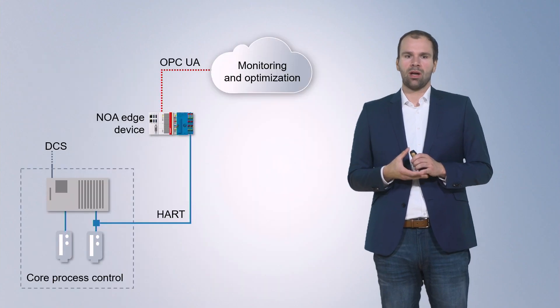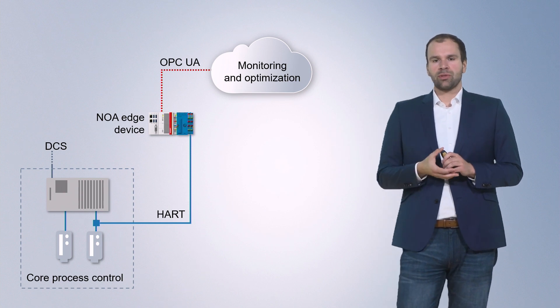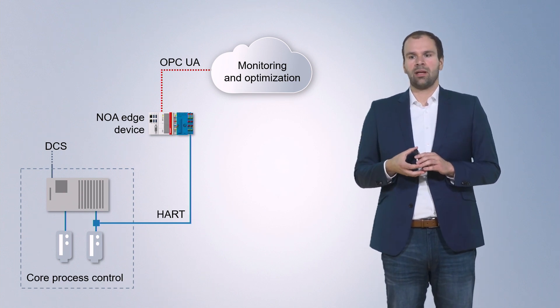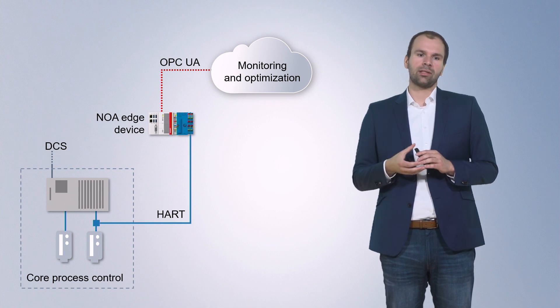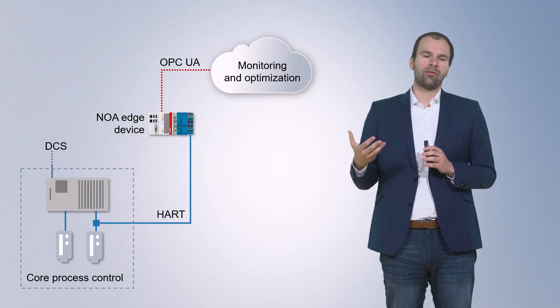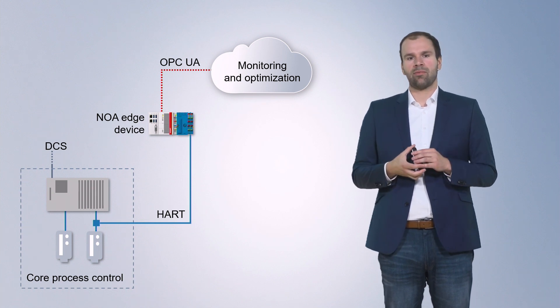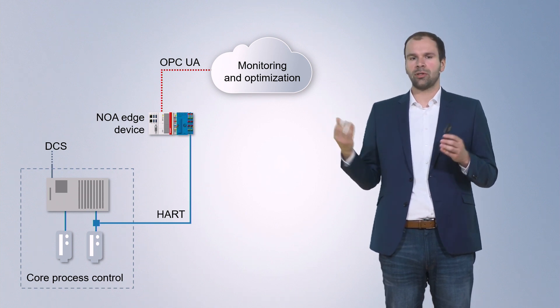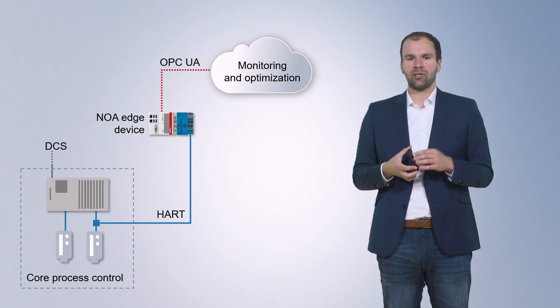This data is then converted inside the edge device, and provided through a standardized OPC UA server to higher-level systems. In our case, we use a standard embedded PC with attached IO EtherCAT cards that connect to the field devices and read the data from the devices. Then we map it to a NOA information model, and provide all the information through the OPC UA server to higher-level systems for monitoring or optimization tasks.